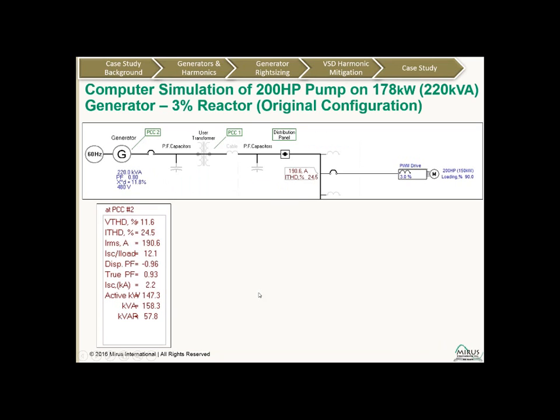So let's look at our case study. Initially, we had the 200 horsepower pump supplied by a 178 kilowatt generator, and there was a 3% line reactor. So we've used our Solve simulation software to create this very simple one line. So we have our generator here. It's 220 kVA or 178 kilowatts. Subtransient reactance of just under 12%. We could put in cables and cable impedances, but we haven't. This is a very short run, so there's very little influence there.